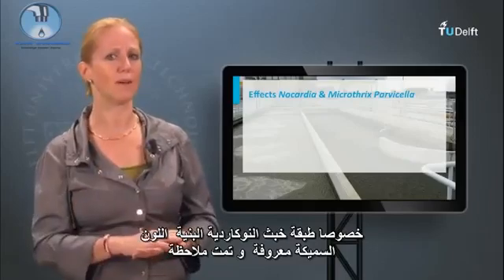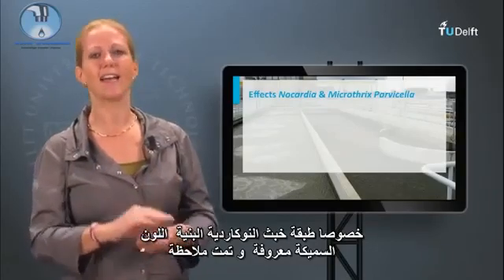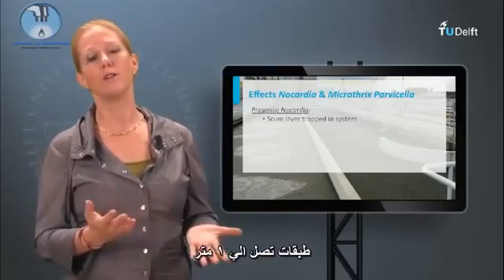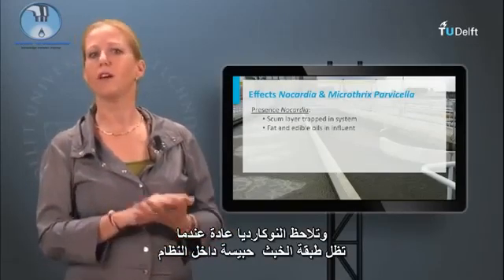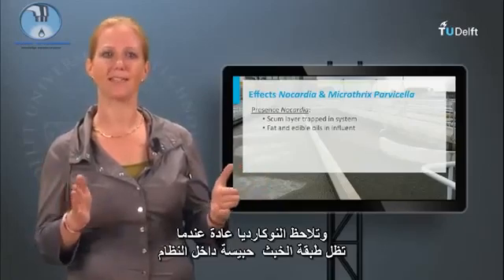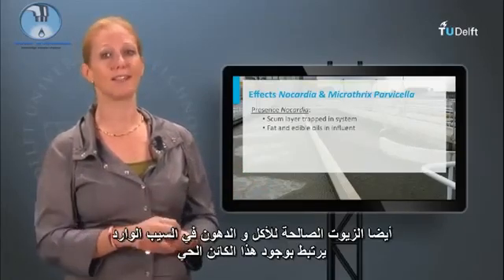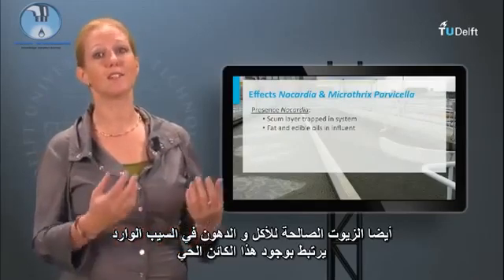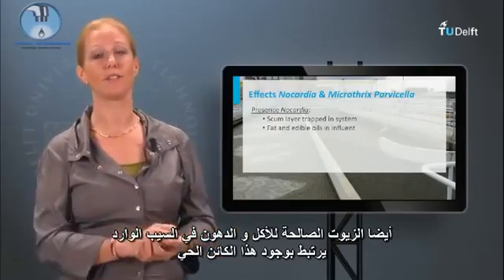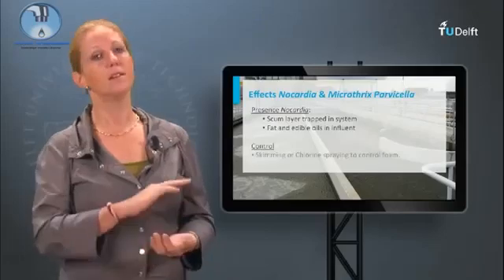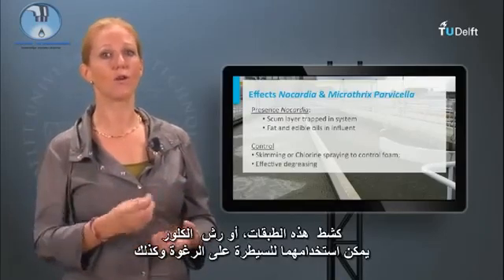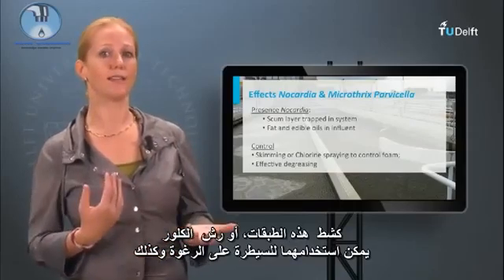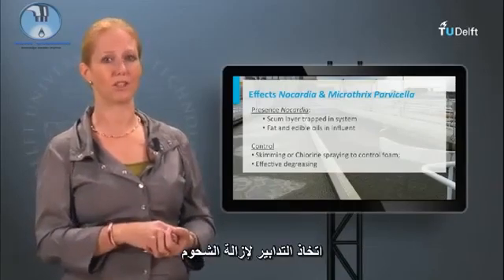Nocardia is typically observed when the scum layer is trapped and kept inside the system. Also, fat and edible oils in the influent are associated with the presence of this organism. Skimming off these layers, or chlorine spraying, can be used to control the foam, as well as effective degreasing measures.